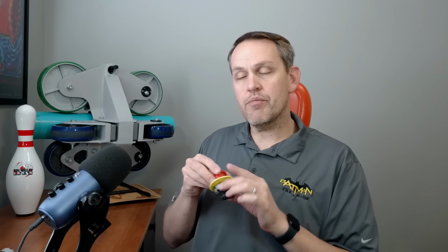Not big, high amperage power. They feed control power to stuff. Like all the motors that run, they take a ton of contactors to pull in and move. All the voltage for those contactors run through the e-stop. So when I push the e-stop, it opens up all the contactors and prevents the big voltage from going out. Remember, controlling rides is all about using small voltage to control really big stuff.